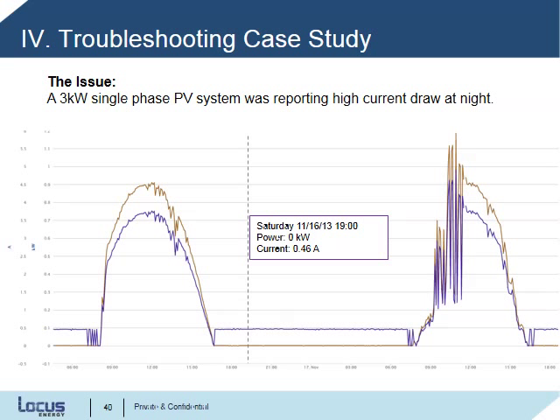An LGate 120 was installed to monitor a 3 kW single-phase PV system. We noticed that the LGate was reporting high current draw at night. In this chart, you can see power graphed in orange and current graphed in purple. At first, we suspected an installation error or a site design flaw, which would probably require a site visit by the installer.